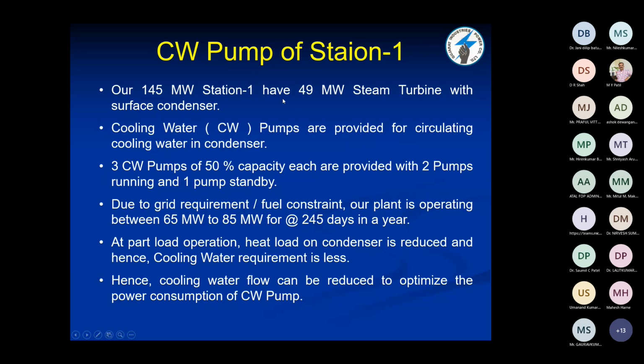Station 1 is having 145 megawatt with 49 megawatt steam turbine with surface condenser. Cooling water pumps are provided for circulating cooling water in condenser. 3 cooling water pumps of 50% capacity each are provided with 2 pumps running and 1 pump standby. Due to grid requirement or fuel constraint, our plant is operating between 65 megawatt to 85 megawatt for 245 days in a year. At part load operation, heat load on condenser is reduced and hence cooling water requirement is less. Hence, cooling water flow can be reduced to optimize the power consumption of cooling water pump. You can understand it because the plant is running at part load, but the cooling water requirement is also low at that point. But the pump is of full capacity. We have to run that pump at full capacity. So there is a higher consumption of power. So to optimize that, we can reduce the flow of cooling water.